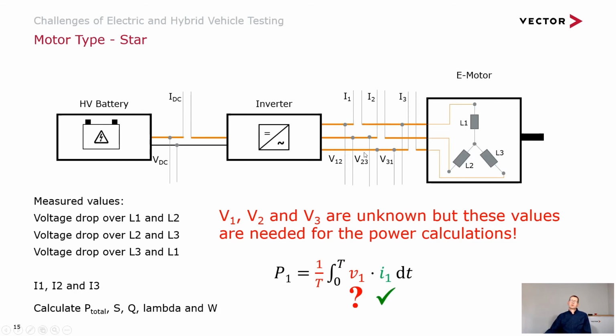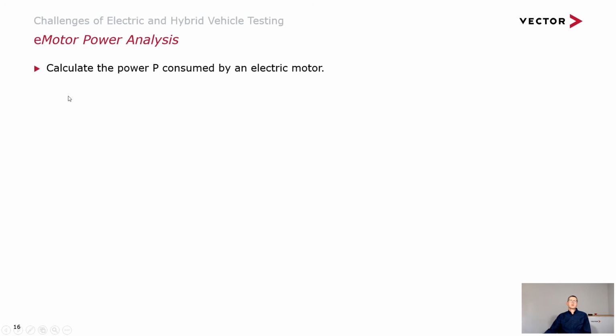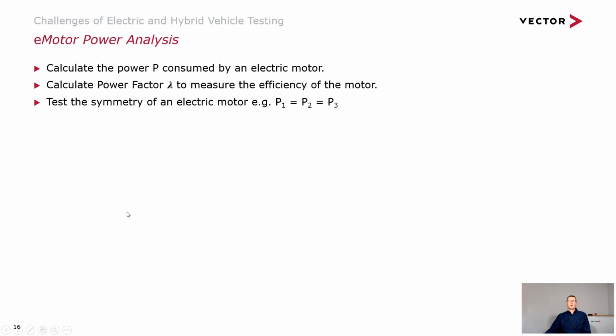So just by purely recording the voltage and current, we can't calculate everything directly from the motor. But with the right analysis software, it's possible to work out those individual parameters to correctly calculate the power of each of the coils. But we can still calculate total power, active, reactive, lambda, and W. So if we can calculate the power of the electric motor, then we can calculate the power factor and we can compare that with the rated value. And therefore, with the right analysis software, we can test the symmetry of the coils, looking at whether there's equal power used by each of the coils.